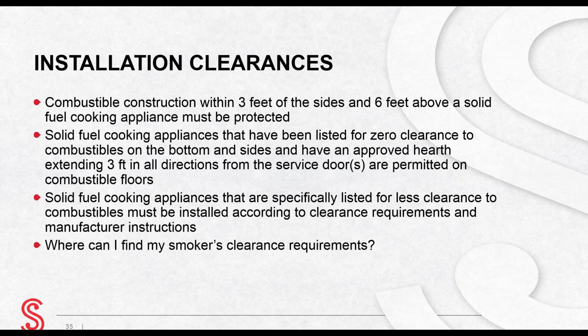Combustible construction within 3 feet of the sides or 6 feet above the solid fuel cooking appliance must be protected in a manner acceptable to the authority having jurisdiction. This means meat smokers should be installed where there is at least 3 feet of space between the smoker and any combustible wall and 6 feet of space above the meat smoker and any combustible ceiling.